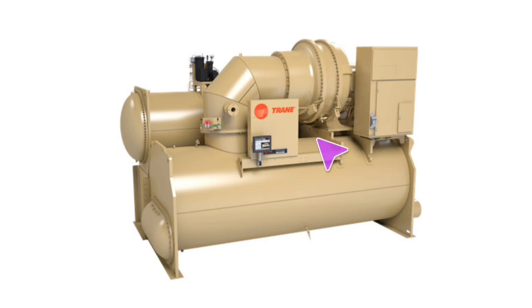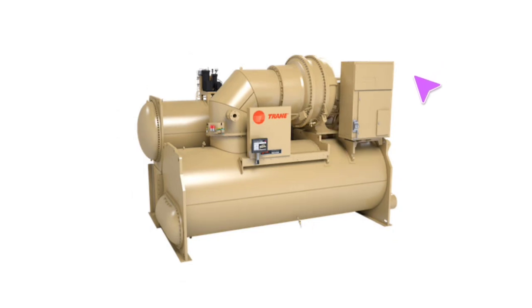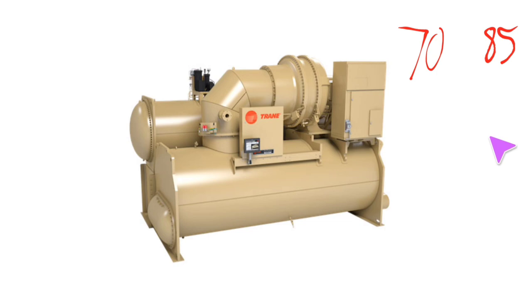They have each other's opposite effects. Let's talk about actual set point values. Since Trane doesn't handle lower lifts as well, I try to run no less than 70 degrees of condenser water on there. But because they do a lot better at the high lift values, I have a lot more confidence running 85 degree condenser water and not have to be too worried about very many issues. Let's say we're talking about a York YK. On the other hand, since they don't run as well on the higher lifts, I try not to allow those plants to go more than 80 degrees, which in the summertime is actually kind of difficult.